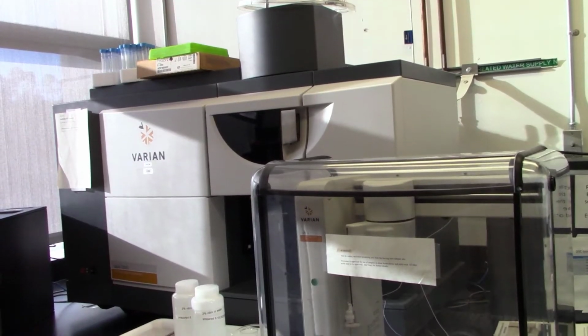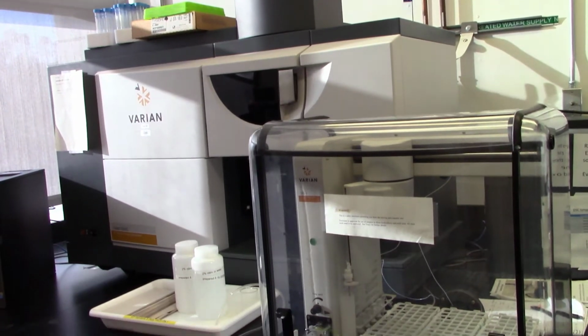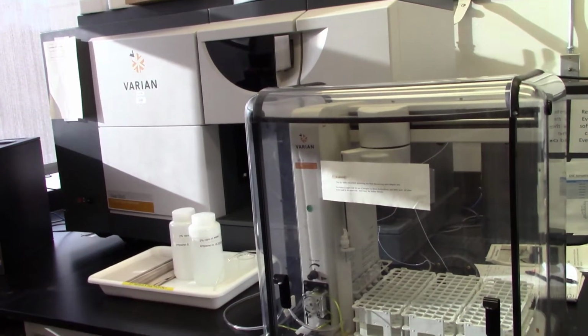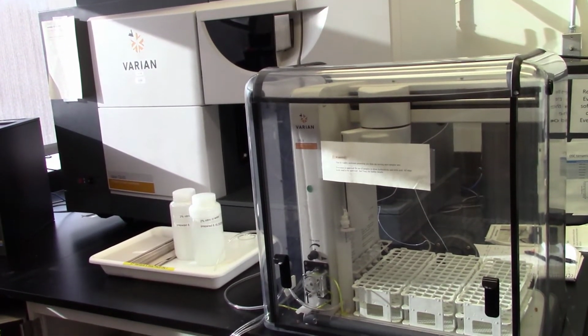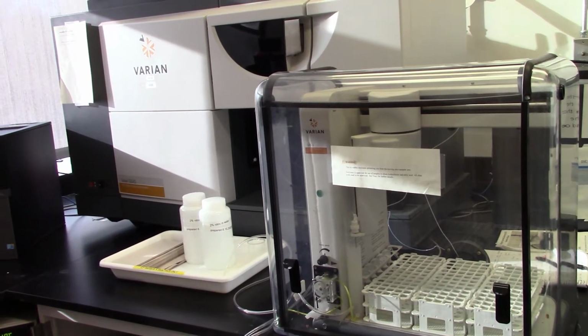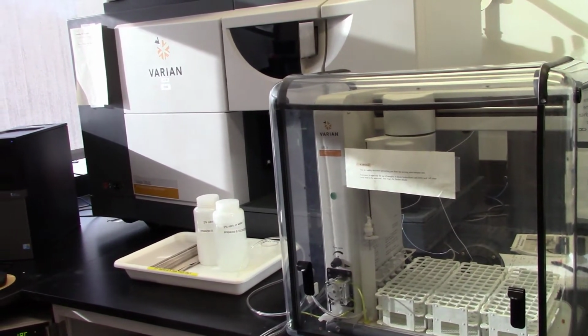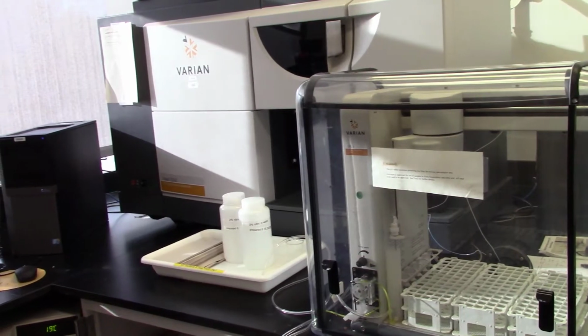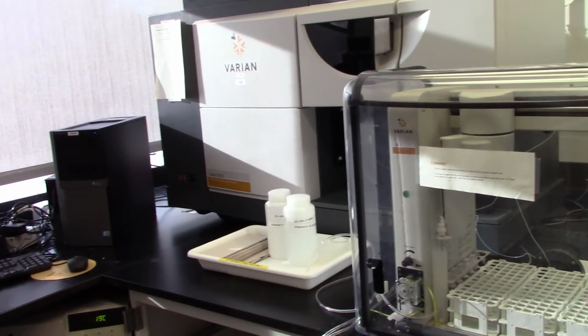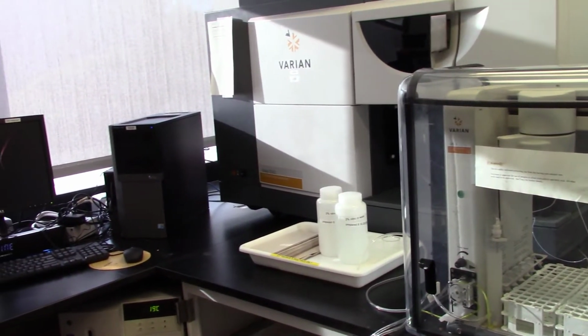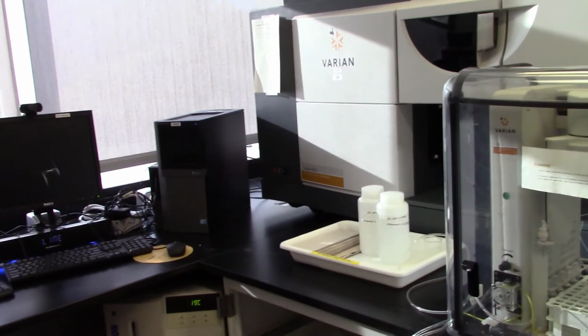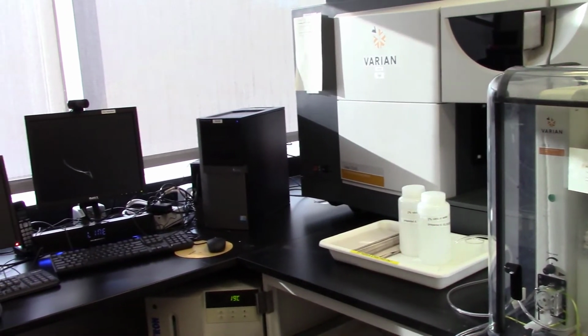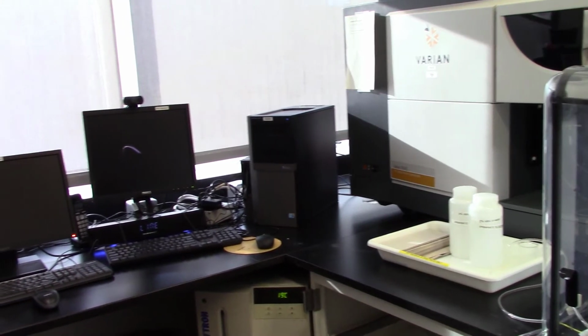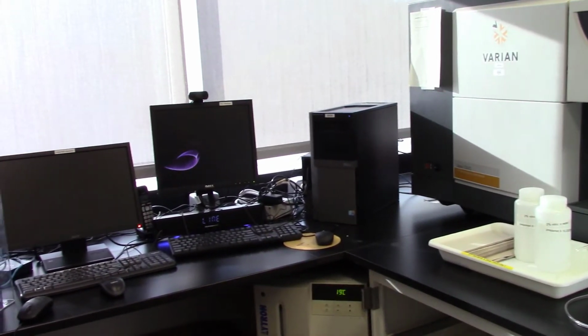The ICP-OES at the Molecular Foundry is equipped with an autosampler to help make elemental analysis go smoothly. It is routinely used to measure concentrations of metals in the parts per million range. When determining whether this instrument is appropriate for your needs, please keep in mind that samples containing fluorine are strictly prohibited, and the measurement of halogens and carbon are not possible using an OES detector.